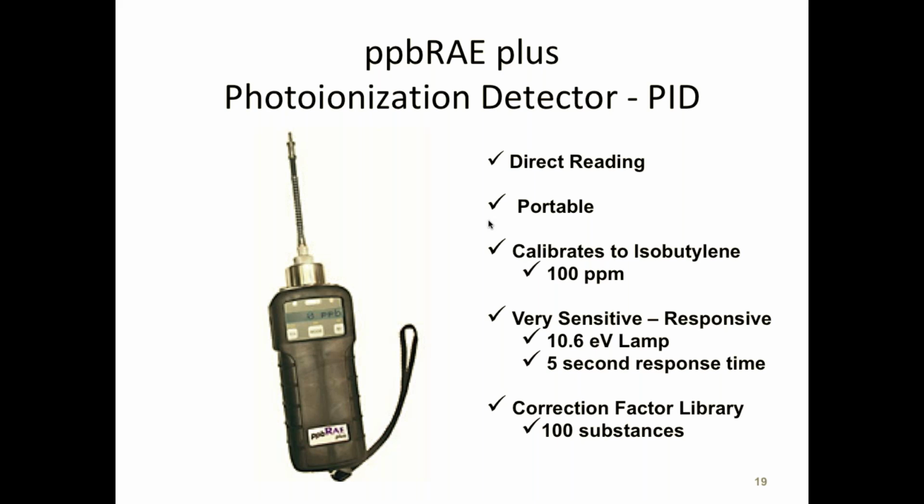Okay, and this has a little pump in it. This one doesn't unfortunately work, but it has a little pump in it. I'm going to show a video of how this actually operates. It has a little pump in it, draws air into this device. It's portable, and it's pretty sensitive to many different gases, literally down to part per billion levels. Now the thing is that this photoionization detector uses a high intensity ultraviolet light to ionize the organic vapors as they're being drawn through here.